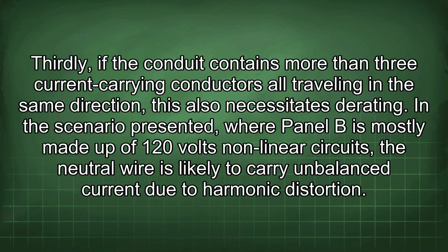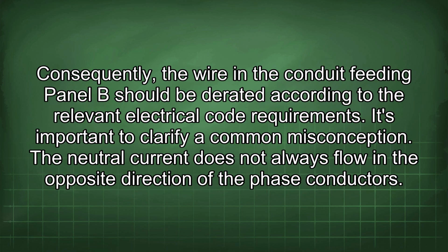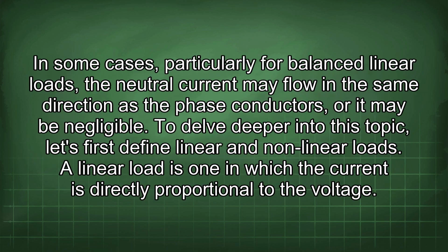necessitates derating. In the scenario presented, where panel B is mostly made up of 120 volts nonlinear circuits, the neutral wire is likely to carry unbalanced current due to harmonic distortion. Consequently, the wire in the conduit feeding panel B should be derated according to the relevant electrical code requirements. It's important to clarify a common misconception. The neutral current does not always flow in the opposite direction of the phase conductors. In some cases, particularly for balanced linear loads, the neutral current may flow in the same direction as the phase conductors, or it may be negligible.